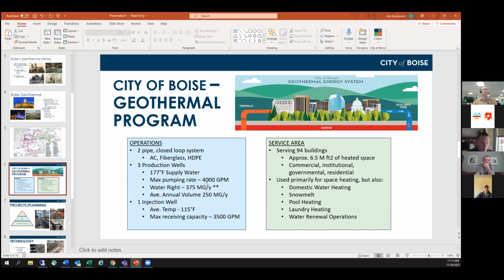Great question. We encourage maximum use of this resource, so there's no minimum temperature to return it at. The average temperature we're seeing most buildings pull off is about a delta T of 50 - that's kind of become the standard. Some buildings can get above that, some struggle to reach a delta T of 50. The buildings that do get above it, some can reach a delta T of 60, 70, and sometimes even 80 degrees off of this water.